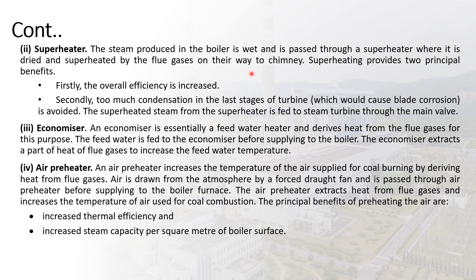The steam produced in the boiler is wet and is passed through a superheater where it is dried and superheated by the flue gases. The superheating provides two principal benefits: overall efficiency is increased, and too much condensation in the last two stages of the turbine — which causes blade corrosion — can be avoided.